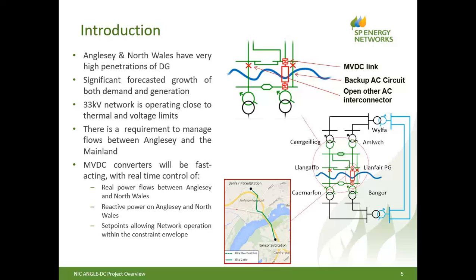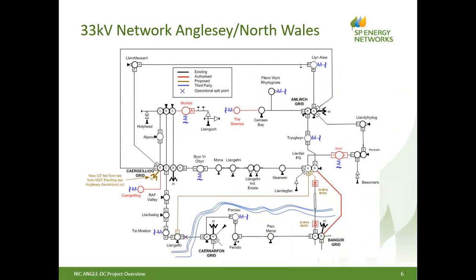Once we've done this, we will then open the other feeders across to the island, and the DC link will be the only connecting point, and that obviously gives us the opportunity to manage power flows. The next slide just gives you an illustration of the system diagram for the 33 kV network on the Anglesey Island and just off it on the Menai Straits. And you can see the circuits there in a bit more detail that I'm actually talking about.